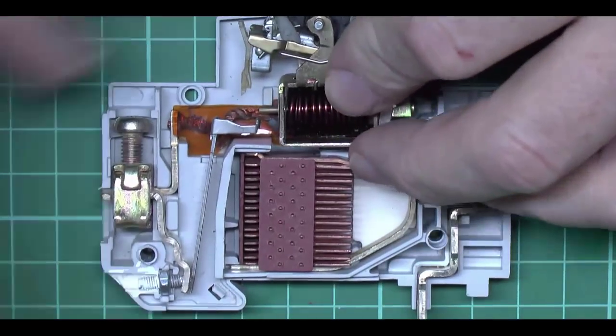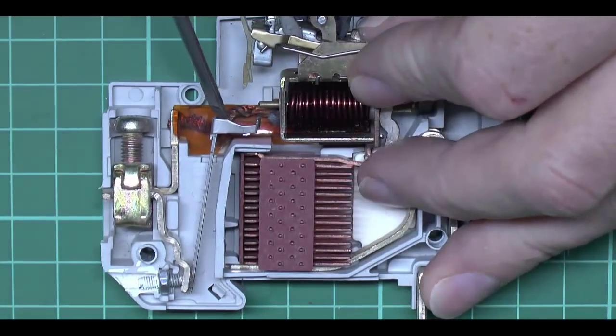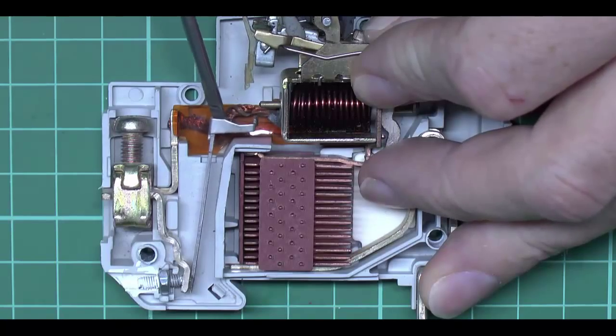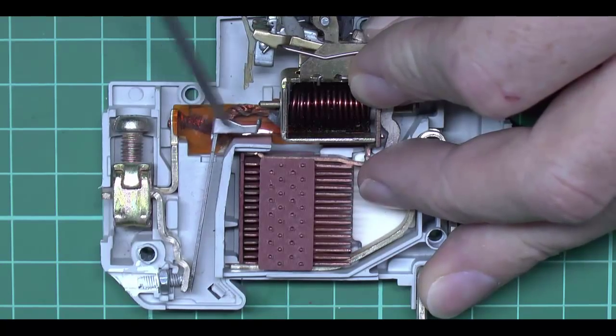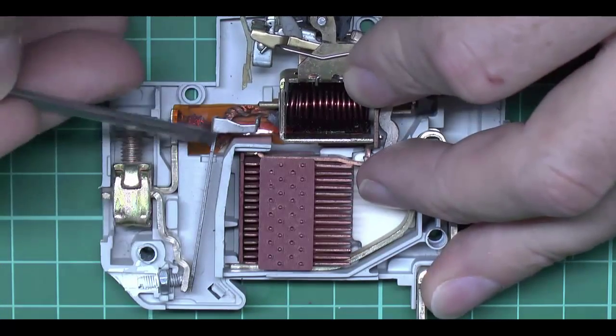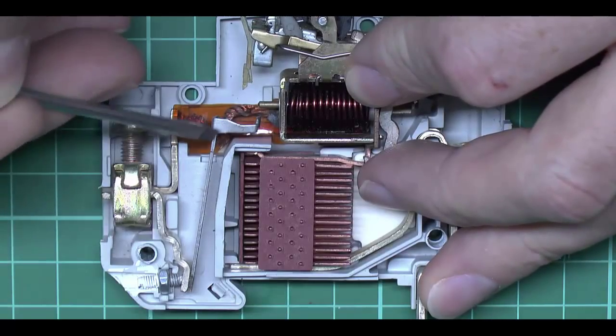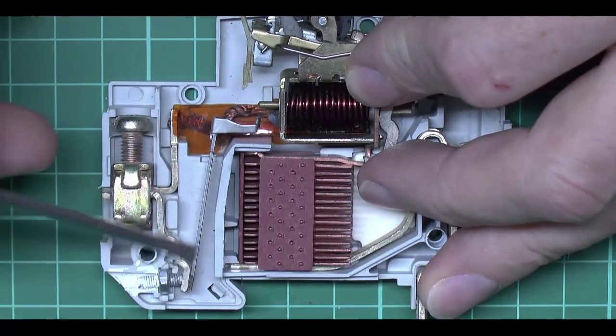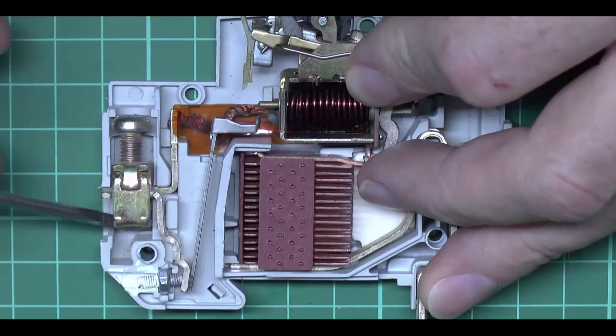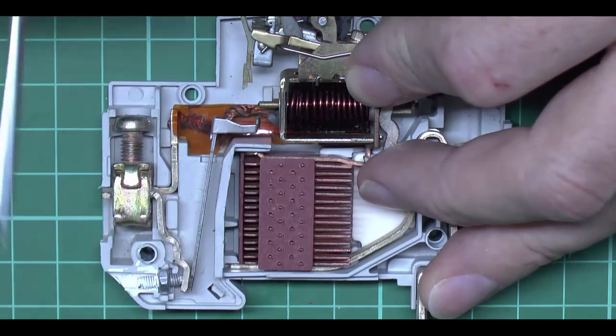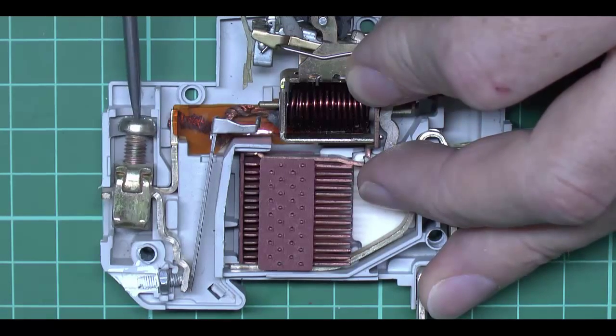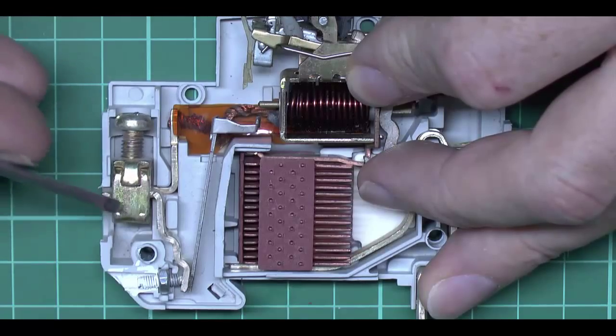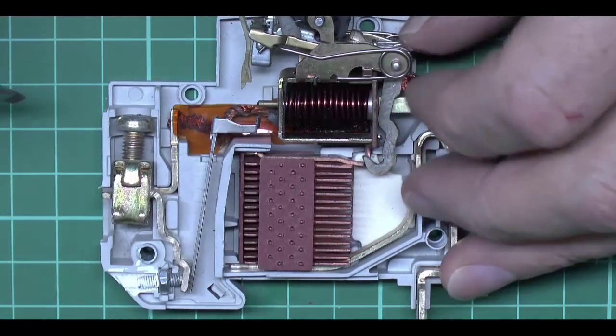Let's put that back in. And the braid actually connects to this movable piece of metal here. And this is a bimetallic strip of the type also used in thermostats. And current continues via this strip here, and then comes back via the terminal and of course out to the circuit wiring that you have. And the screw here is just used to tighten up and pull onto the wire so it's secured in position.